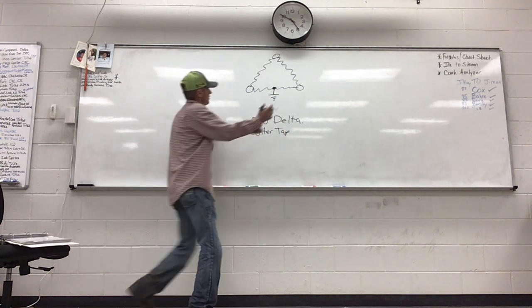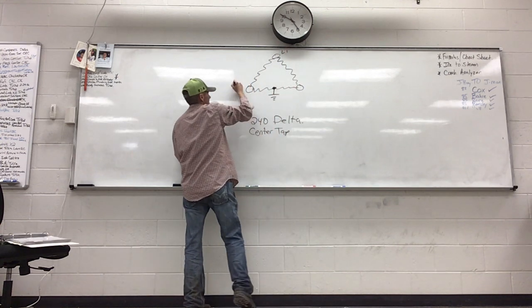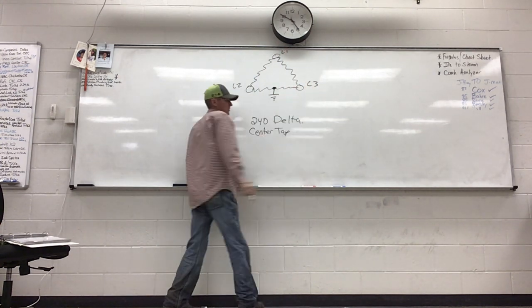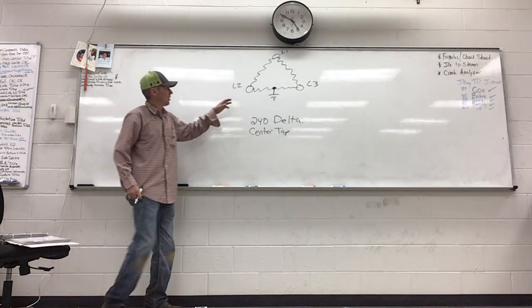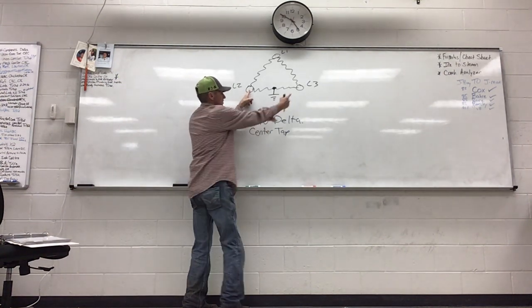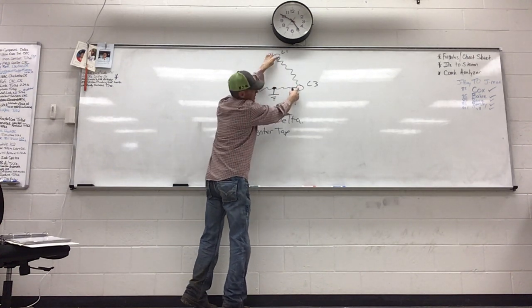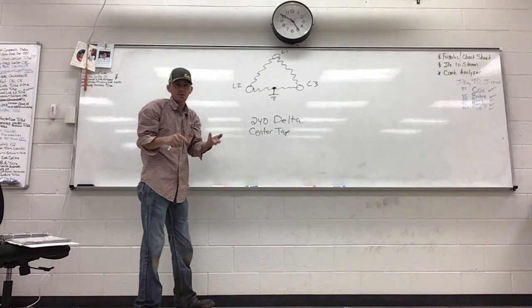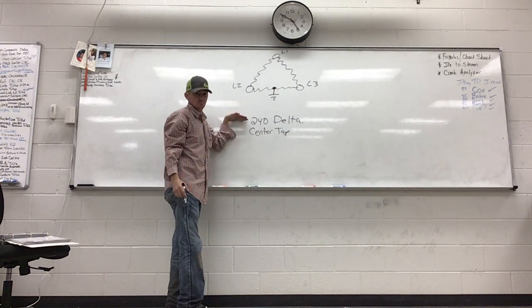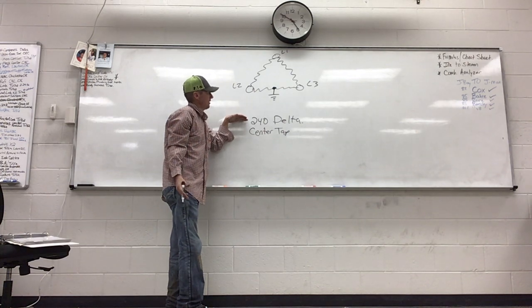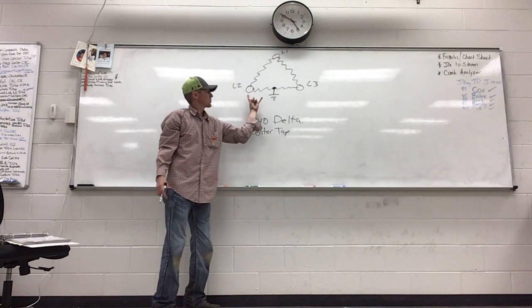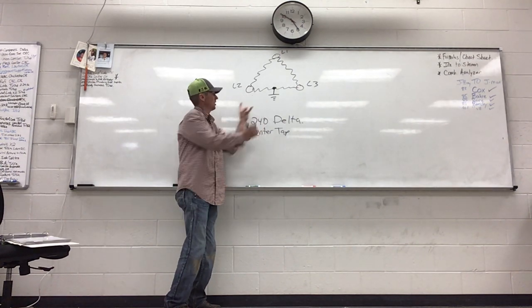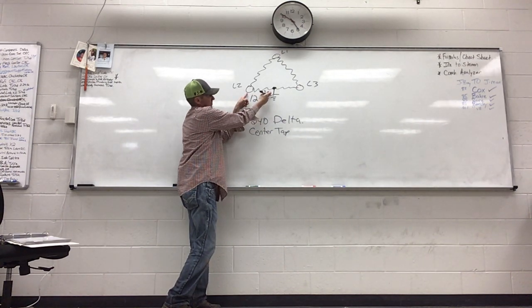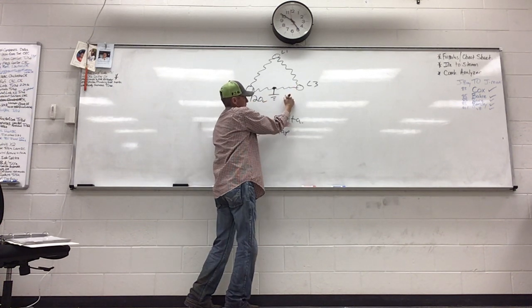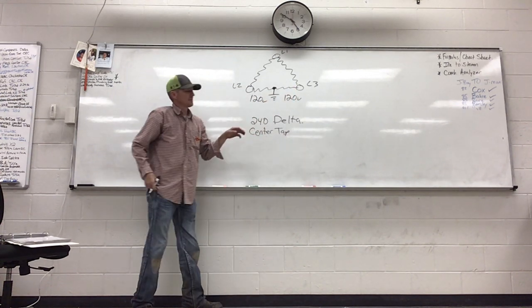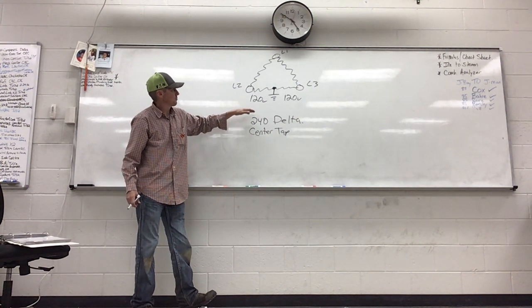So on this one I'm going to give it some designations. That's L1, this is L2, and we'll say this is L3. I'm just making those up. So between any leg to any leg, 1 to 2, 2 to 3, whatever, we're going to get 240 volts. But the kicker on this one is from L2 to neutral ground we'll get 120 volts. From 3 to neutral ground we're going to get 120 volts. But this is the one, the center tap, the 240 Delta, that's got the stinger leg.